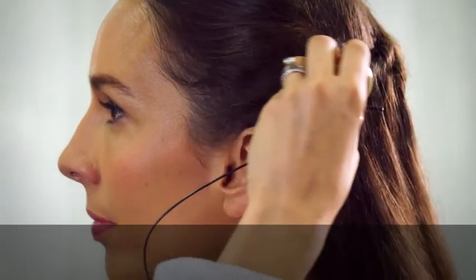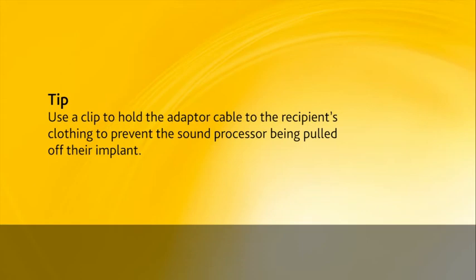Put the Kanso on your recipient. Use a clip to hold the adapter cable to the recipient's clothing to prevent the sound processor being pulled off their implant. Start the Cochlear Fitting software and program your recipient's Kanso.